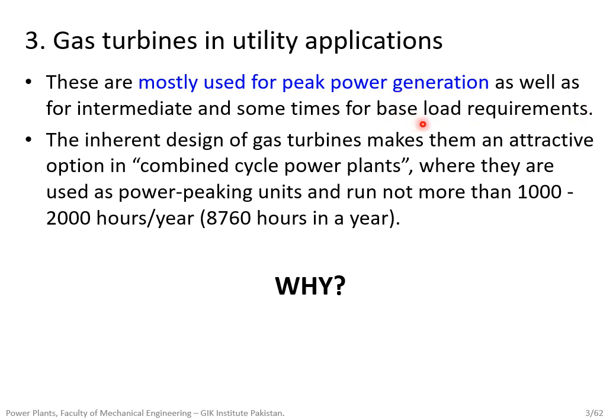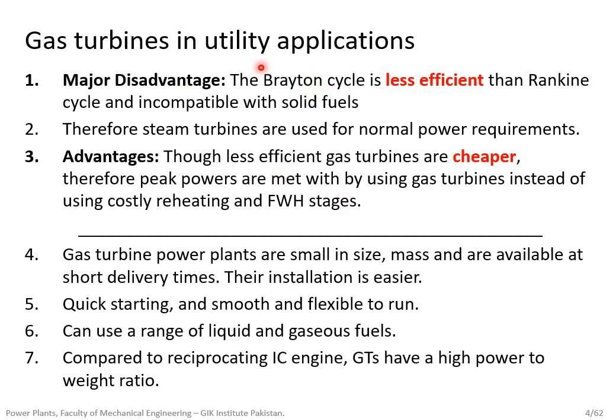Gas turbines are normally not used for baseload applications. The primary reason is that they are less efficient than the Rankine cycle and are incompatible with solid fuels. Their primary advantages are that they are cheaper due to small size and mass, and they are able to deliver power in a very short time — easier to install, quick to run, smooth and flexible. So for peak power demands, gas turbines are normally used.